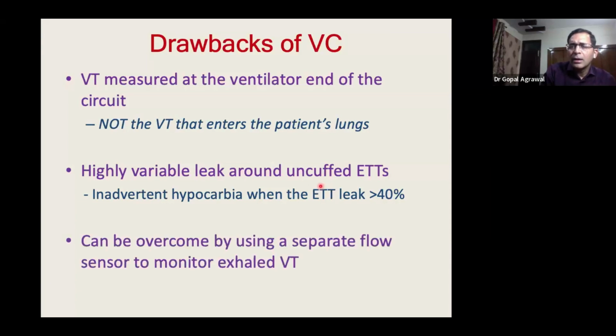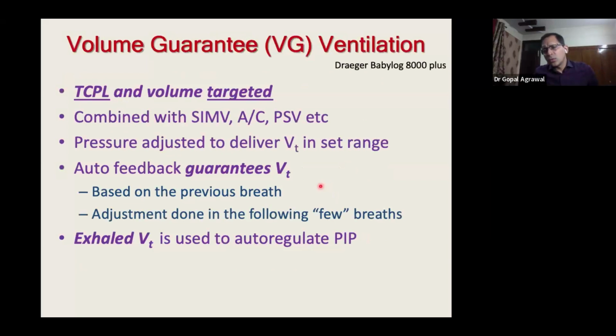But nowadays there are machines which measure the actual tidal volume. That is a better sensor, a better module for measuring the tidal volume. So to bypass and overcome all this, volume guarantee ventilation has come up. Various machines have different names, but by default it's a volume guarantee, where it is a time controlled pressure limited ventilation and volume targeted. We'll see how it works. It can be combined with SIMV, assist control, and PSV. That's why it's a hybrid mode. The basic mode is TCPL, but it's volume targeted.